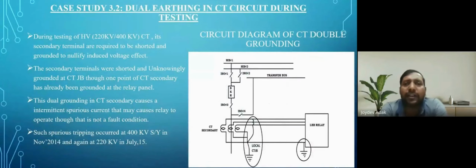Now coming to the dual earthing of the CT circuit. This is the current transformer, these are the two main buses, main bus 1 and main bus 2, and the transformer bus. This is the two main and one transformer bus scheme. Normally, the current transformer circuit, which is a protection circuit, is grounded at either the field end or the relay end. This is the LBB relay, the local breaker backup relay. Normally, grounding should be at any one end only.